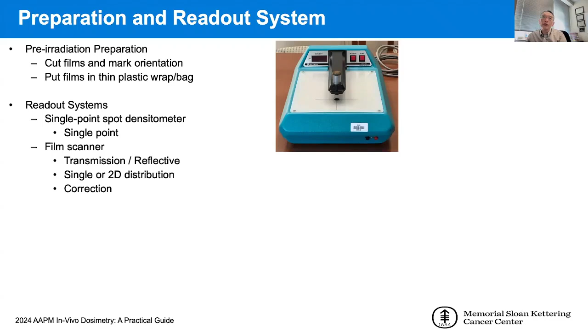When we come to readout systems, there is a single point spot densitometer. This is an example of that, where you can place a piece of film right in the middle of the reading area and read out the density. But this is only good for single point measurements. So just keep that in mind if you plan to use it. Alternatively, you can use a film scanner. It can be transmission type or reflective type. And here's an example of that, which can be used for single point or 2D dose distribution. For 2D dose distribution, you really need to also think about correction for the flatbed scanner in terms of uniformity or lateral correction.